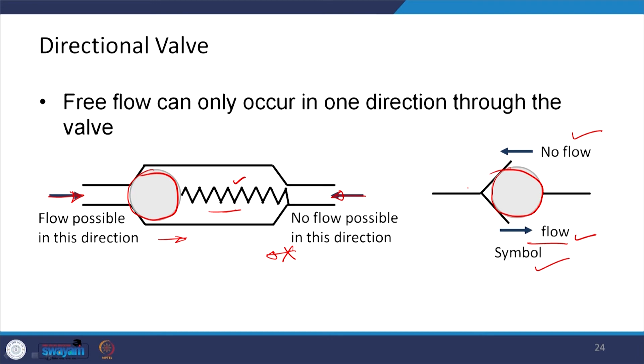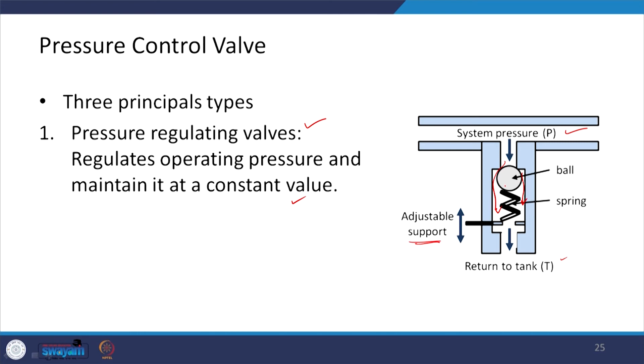Then there are pressure control valves which are used in these systems. There are 3 principal types. One is the pressure regulating valve, and they regulate operating pressure and maintain a constant value. Here the system basically consists of something like this. You have a system pressure here, and if your pressure exceeds, this ball is pressed and of course, whatever your working fluid is, that is released. And the setting of the pressure, at what pressure it should be released, can be done with the help of this adjustable support.